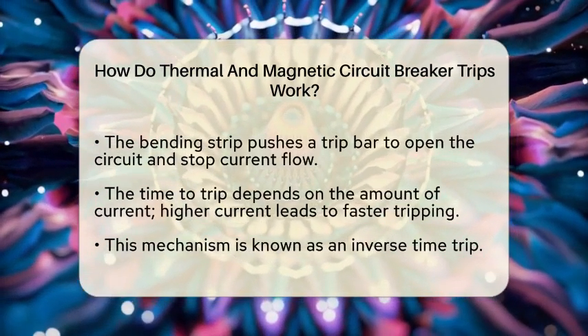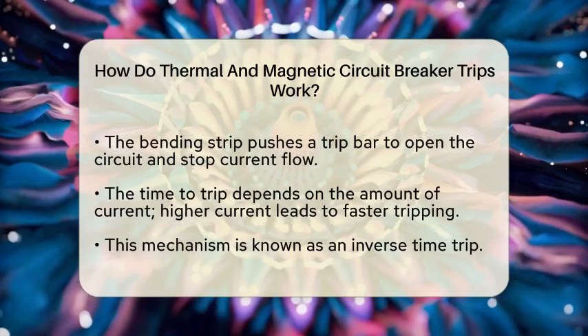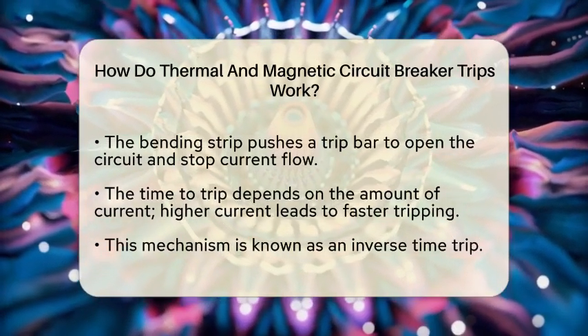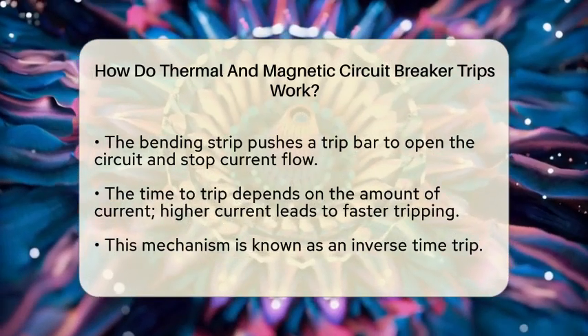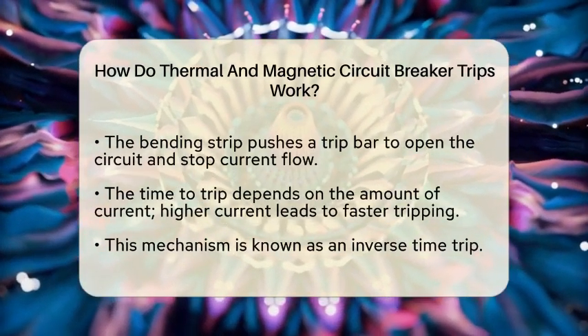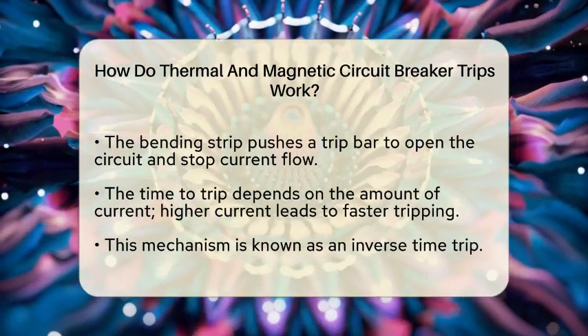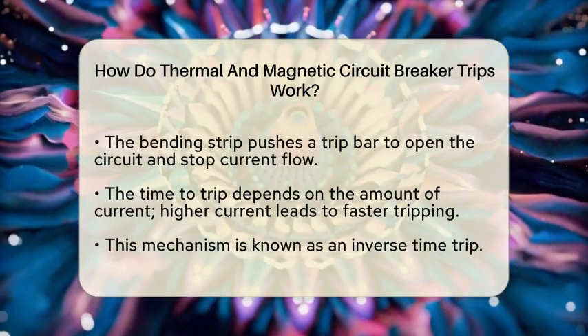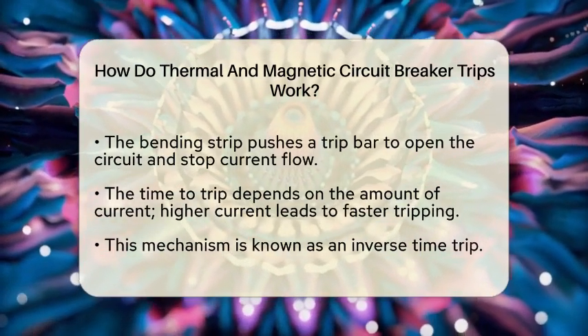This bending action pushes a trip bar that opens the circuit breaker, stopping the current flow. The time it takes for this to happen depends on how much current is flowing. More current means the breaker will trip faster. This is why it is called an inverse time trip.